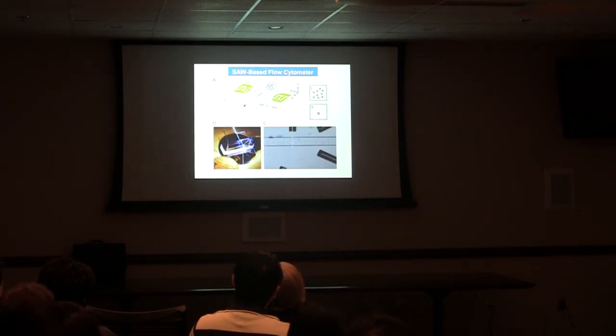So once we demonstrate focusing, we couple that with optics to detect it, and we shine light. One optic fiber to shine light, and three optic fibers to detect signals. We detect three different kinds of signals: forward scatter, side scatter, and fluorescence.